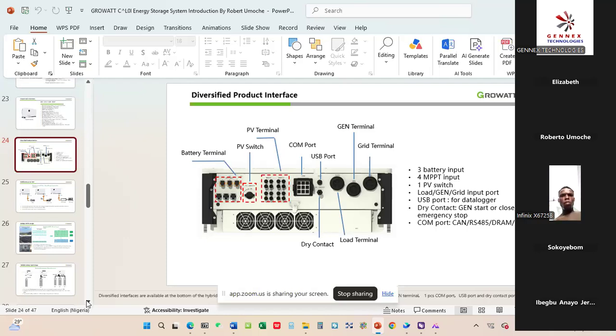And then we have the generator port and the grid port. Some inverters don't have these fixtures. If you must connect your generator or NEPA, you must introduce an external changeover switch. But this one has everything embedded, like an ATS. You can run your generator cable directly to the inverter, and also run your grid input cable directly to the inverter. So it all depends on which one is available. The inverter automatically switches without needing any human intervention.